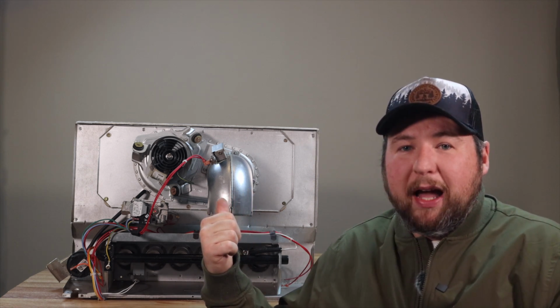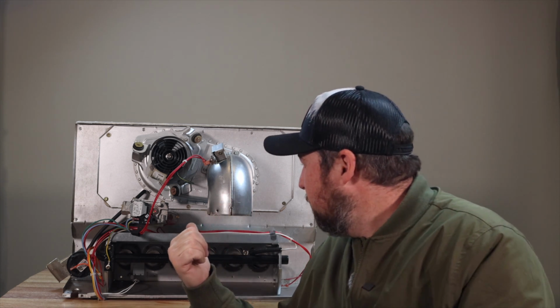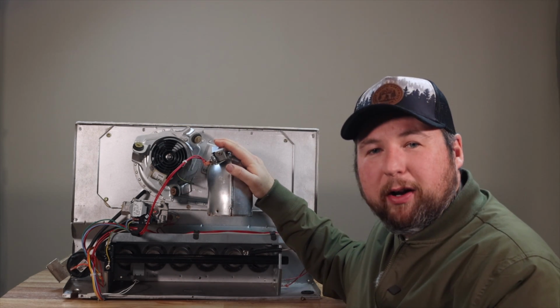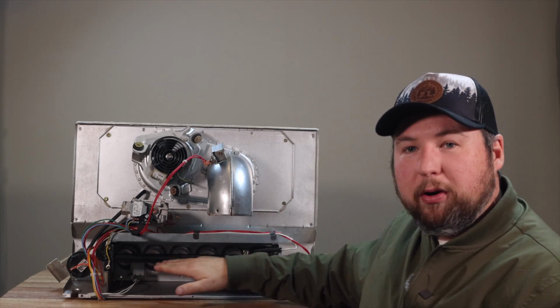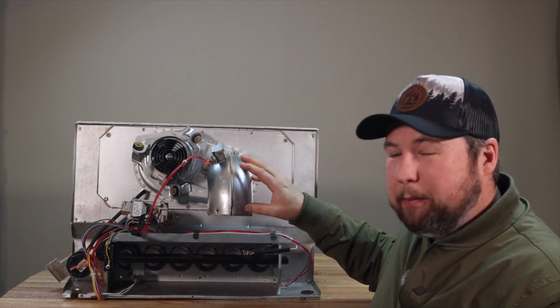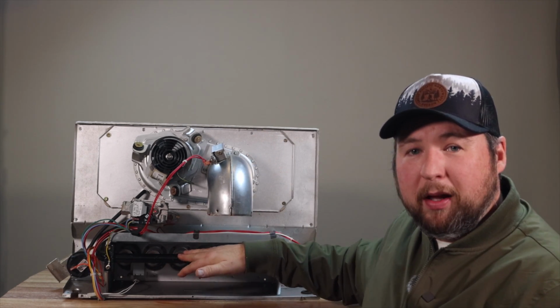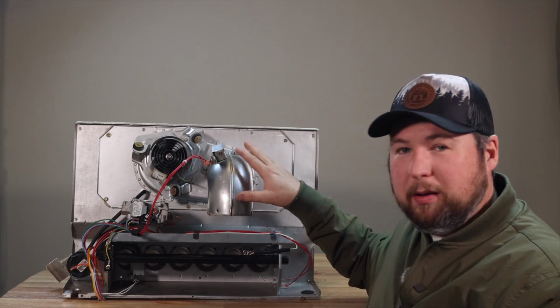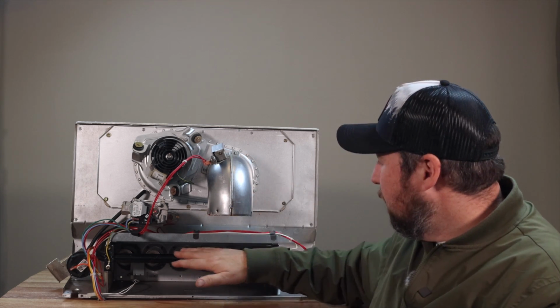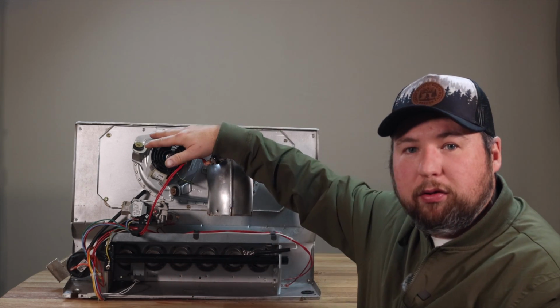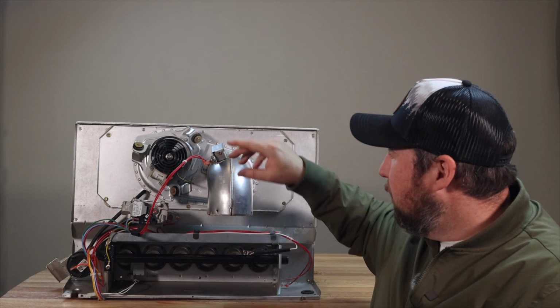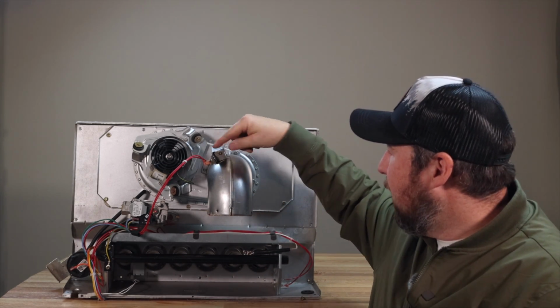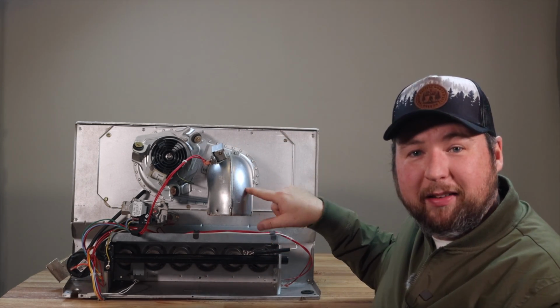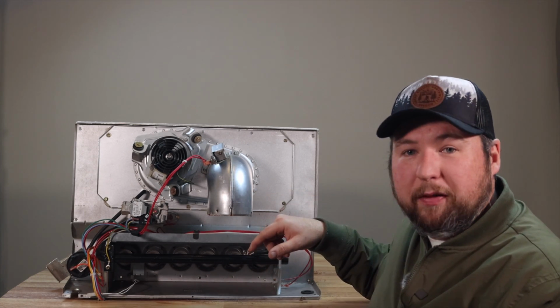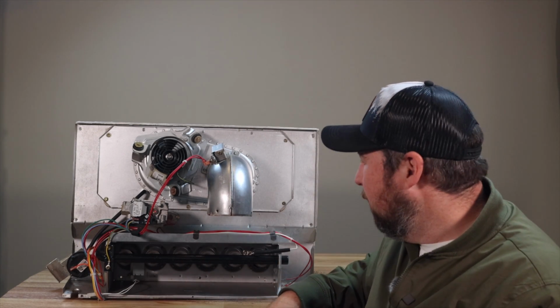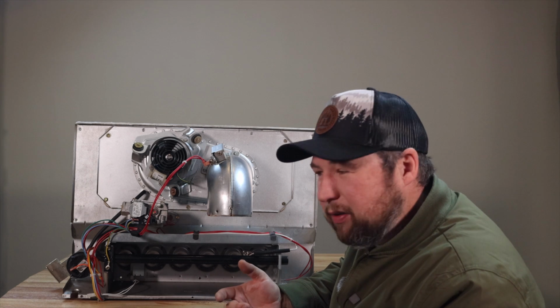But anyway, right here we have a heat exchanger. This is actually going to be a serpentine. This is off of a Carrier unit. So you've got your burners down here, and this is going to be for an 80%er, so you always have your burners on the bottom, assuming it's an upflow. So this is going to be an upflow configuration. You're going to have burners on the bottom, inducer on the top. It's going to burn on the bottom, and the inducer is going to pull it through the heat exchanger and out the exhaust. Now you can see this is pointed down because this was a downflow. So if it's a downflow, basically you flip it upside down. But that's pretty much how you can tell.